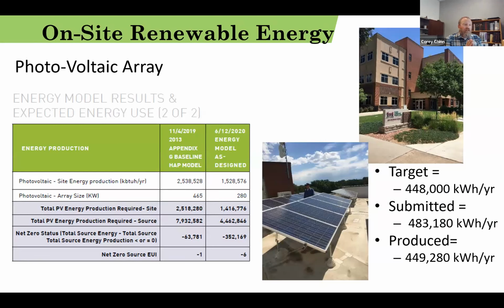If we looked at our baseline building, our PV array would have needed to be 465 kW. As designed and as modeled, we got it down to 280 kW. So at $3 an installed watt, you can do the math real quick there, right? $3 times the difference here times 1,000 equals your cost savings, your capital cost investment saving. I've done that math before, but I don't recall it right now off the top of my head. So by doing those first steps of the equation, we've reduced the overall size.